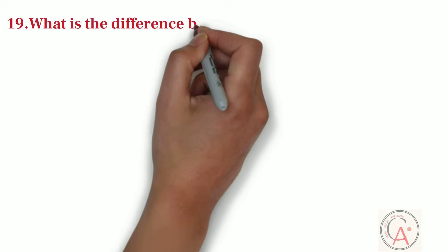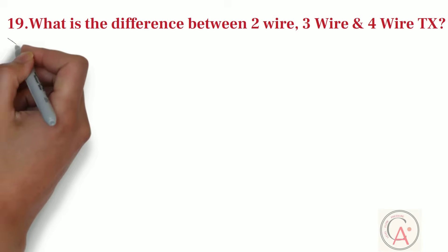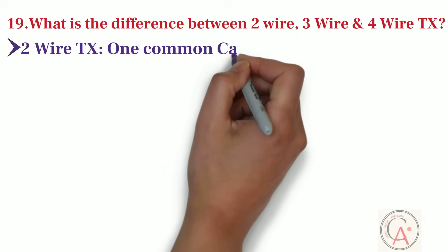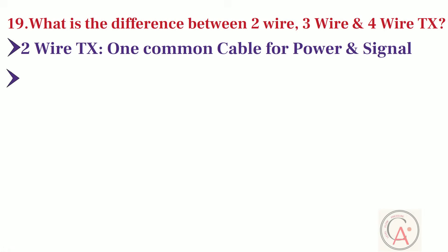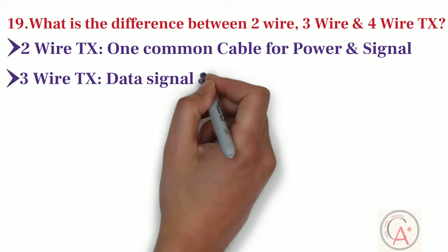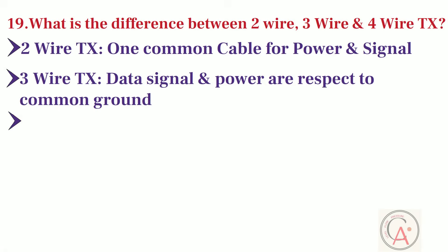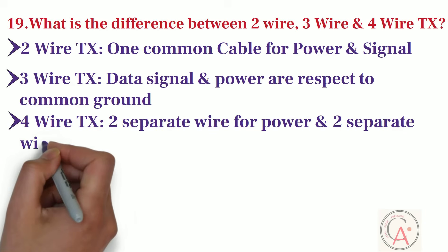Now, the most important question is, what is the difference between two-wire, three-wire and four-wire transmitter? In a two-wire transmitter, there is one common cable for power and signal. While in three-wire transmitter, data signal and power are respect to common ground. And in four-wire transmitter, two separate wire for power and two separate wire for signal.